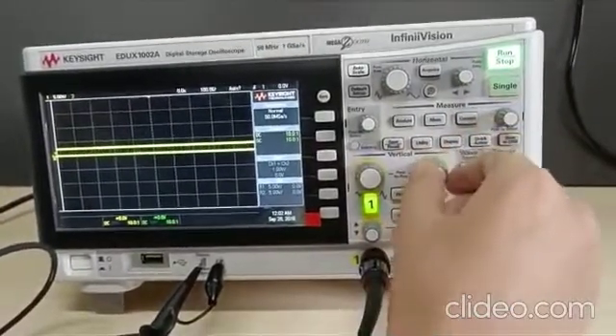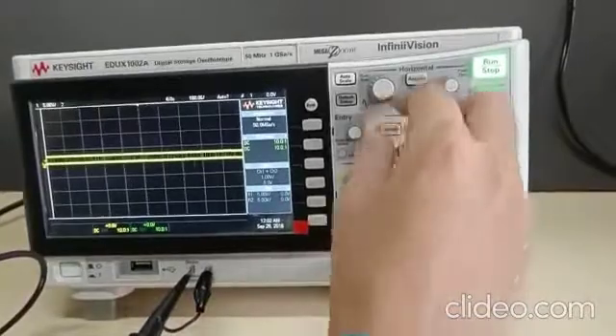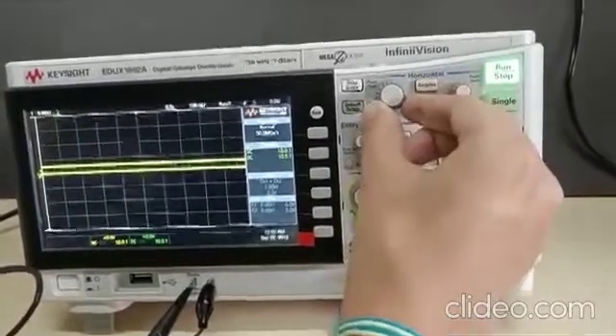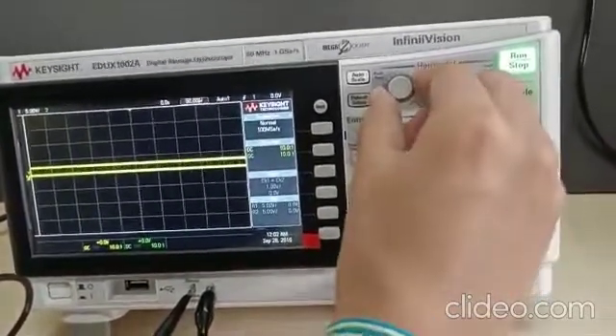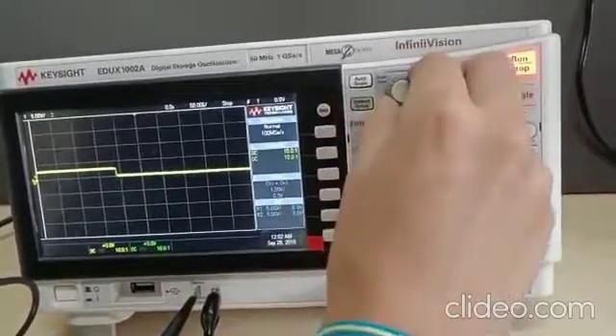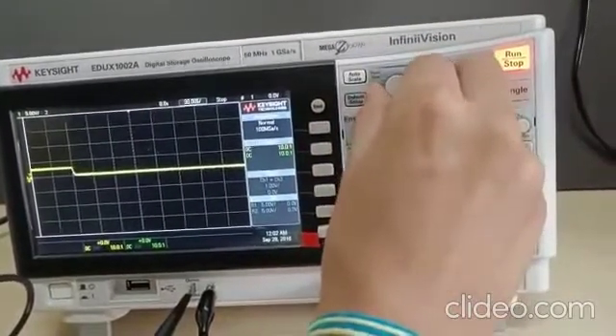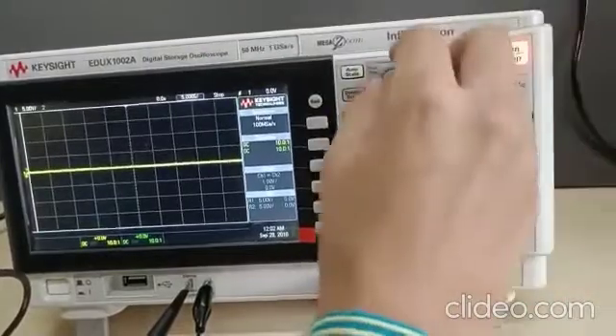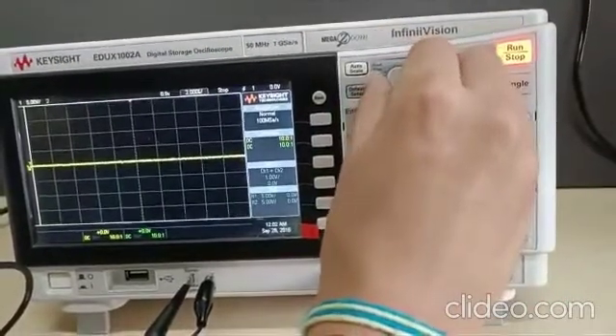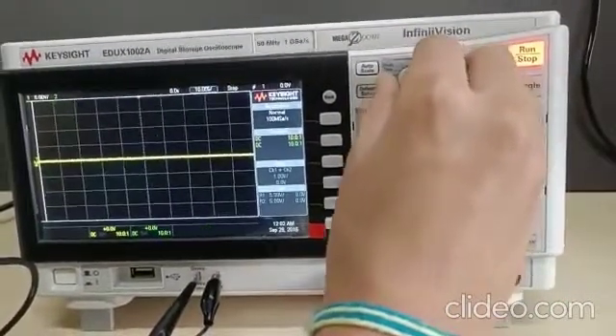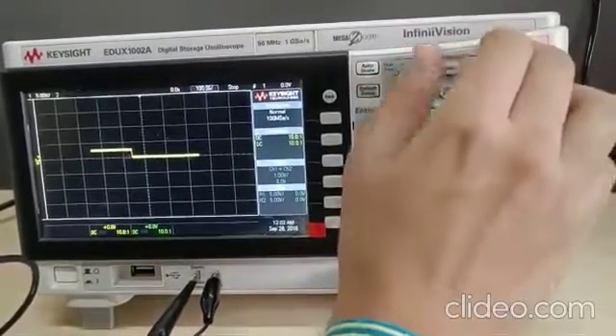And now we will move on to time per division. The time per division knob is on the horizontal scale. By moving time per division clockwise, we reduce the time per division scale. And by moving it anti-clockwise, we increase the time per division scale.